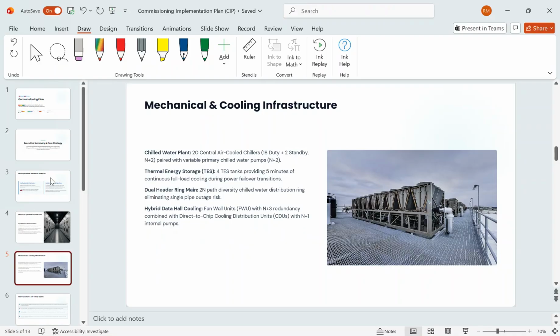It has a dual header ring which provides a 2N path for chilled water distribution, eliminating single pipe outage risk. Hybrid data hall cooling: it comprises fan wall units with N plus 3 redundancy, combined with CDUs, which we call cooling distribution units, at N plus 1.